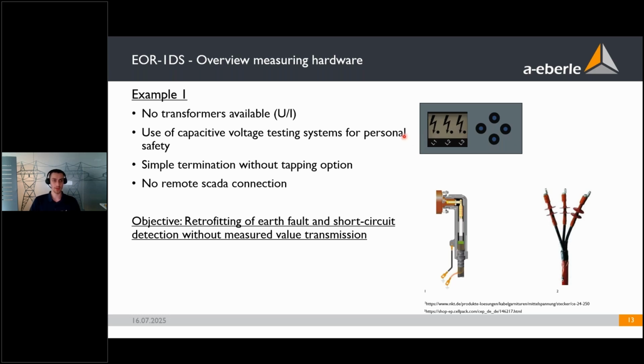Example number one would be that you have a station without transformers available, so no voltage or current transformer. You have a capacitive voltage testing system installed anyway for personal safety. As you can see here, you have these voltage indicators for each phase. You also have a simple termination without a tapping option, so you can't tap your termination for measurement, and you do not have a remote SCADA connection. In this station, your objective would be retrofitting of earth fault and short circuit detection without measurement value transmission.